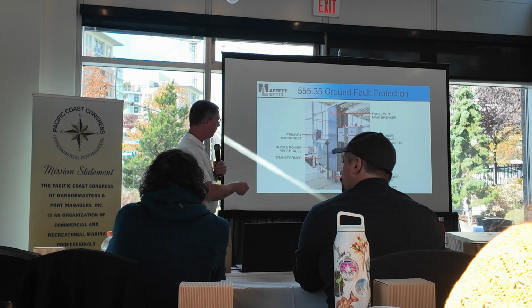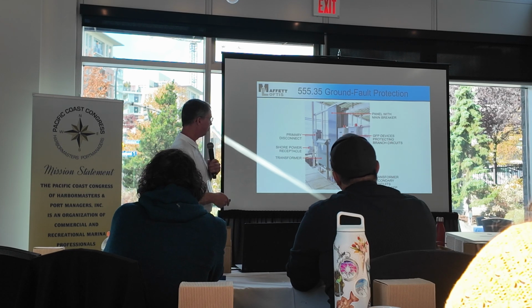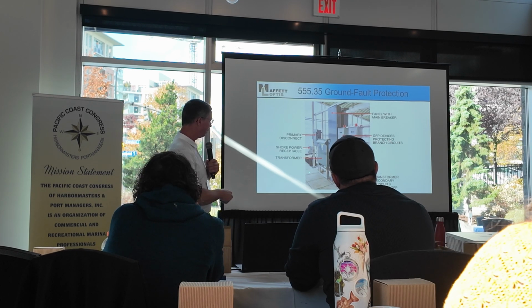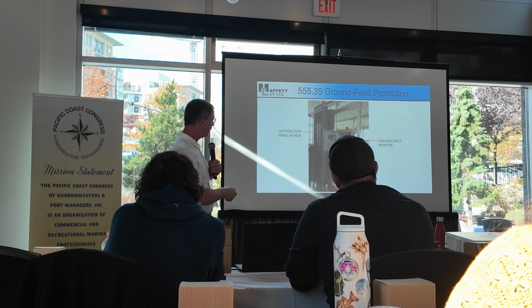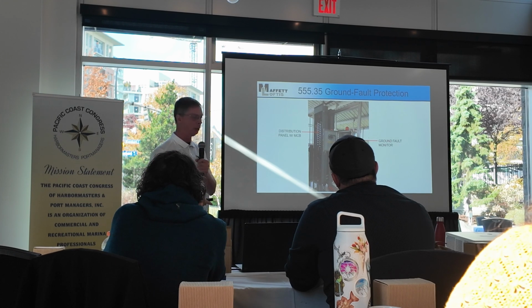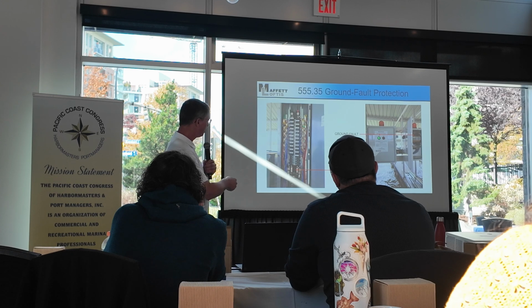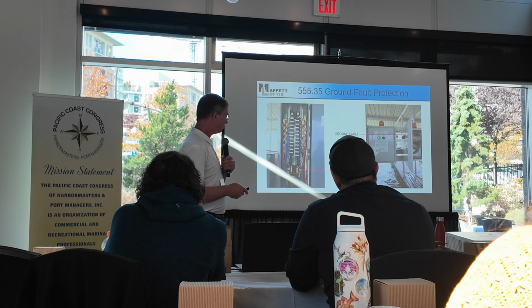Okay, and here are some devices. This is actually from Bender with a 480 system coming in. There's the relay, an RCMS490, which is a field settable relay. Here are the CTs that are doing that. I'm going to talk about the CTs in just a moment.